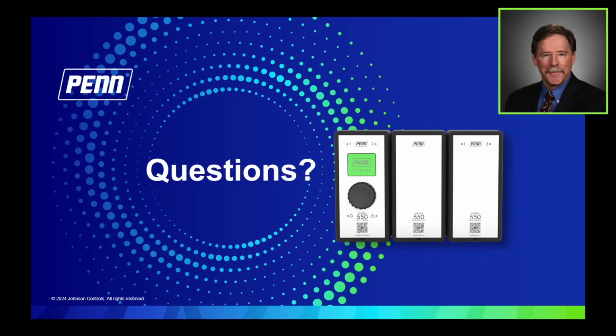Okay, it's a wireless connected device, so it doesn't require any special communications protocol. As I mentioned during the session, when we mean the backplane, there's six pins that connect the control module to a power module and then to expansion modules. And of course, the A2L sensors are running on that backplane. That backplane is Modbus RS485.